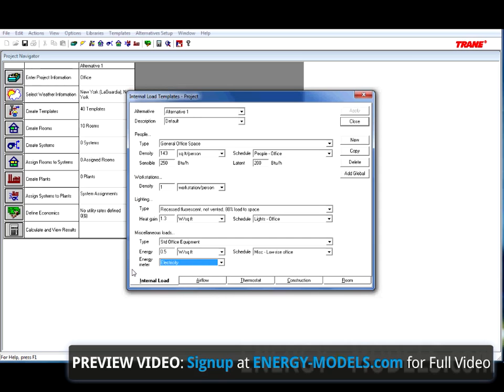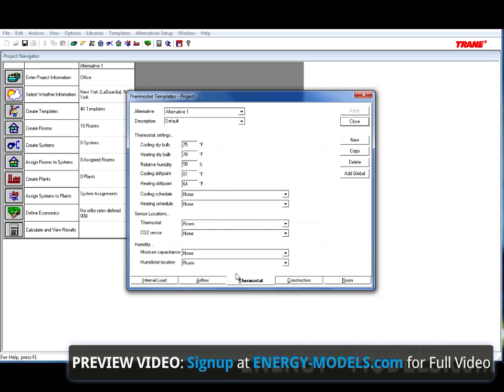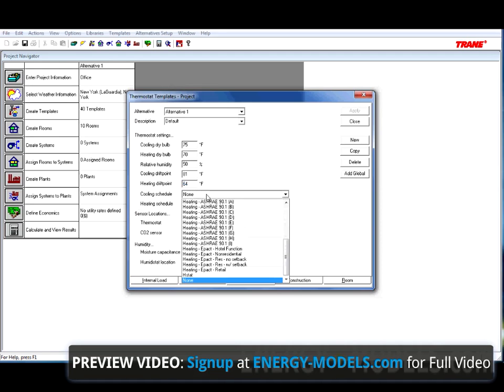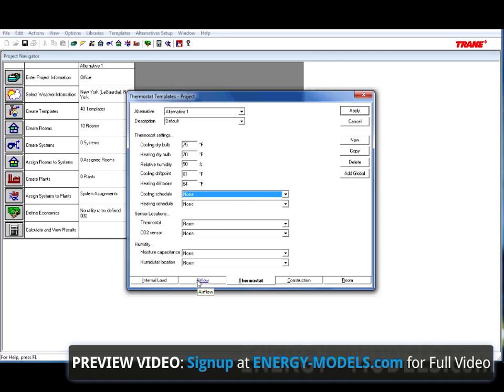The most notable difference is in the thermostat template. The thermostat drift points and cooling and heating schedules are now enabled. A thermostat schedule can be used for scheduling set points at different hours in the day. However, if a room only has two modes, occupied and unoccupied, it is likely that a thermostat schedule can be replaced by entering drift points.